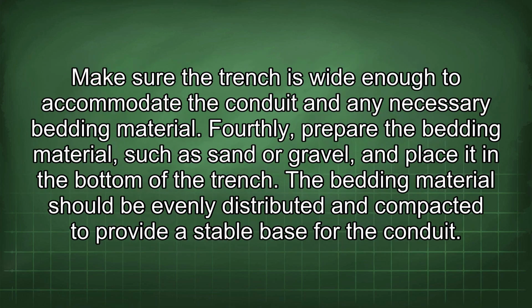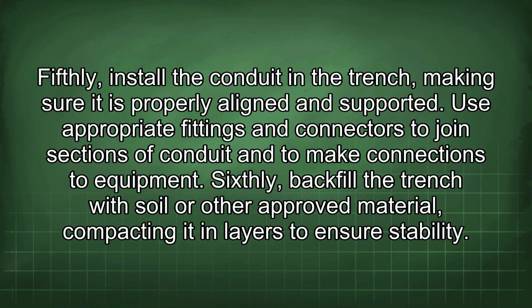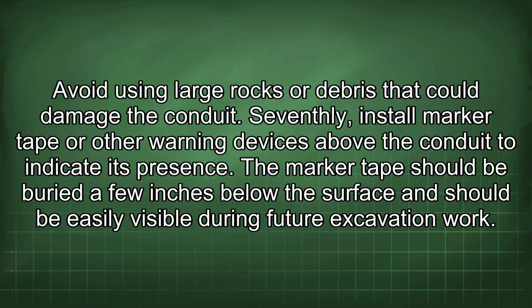Make sure the trench is wide enough to accommodate the conduit and any necessary bedding material. Fourthly, prepare the bedding material, such as sand or gravel, and place it in the bottom of the trench. The bedding material should be evenly distributed and compacted to provide a stable base for the conduit. Fifthly, install the conduit in the trench, making sure it is properly aligned and supported. Use appropriate fittings and connectors to join sections of conduit and to make connections to equipment. Sixthly, backfill the trench with soil or other approved material, compacting it in layers to ensure stability. Avoid using large rocks or debris that could damage the conduit.